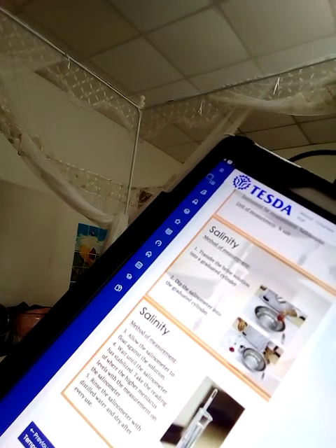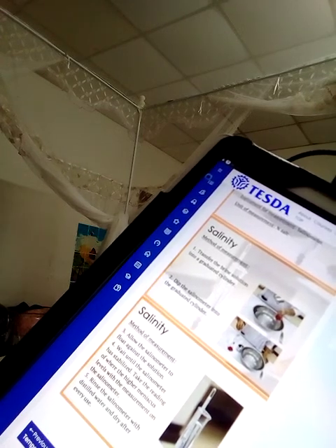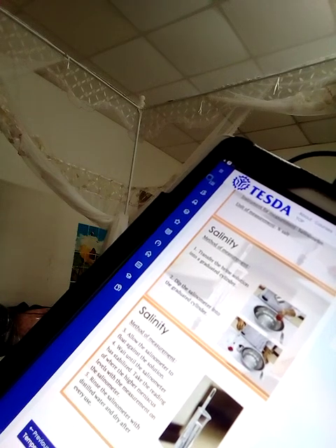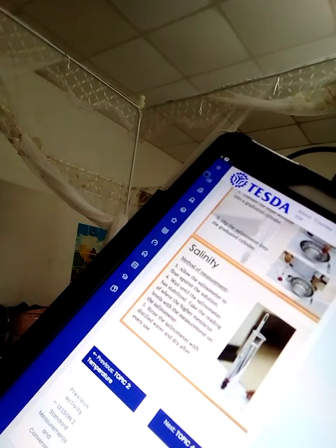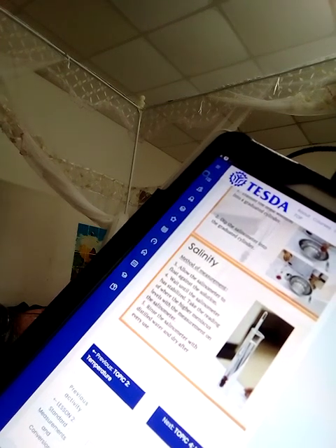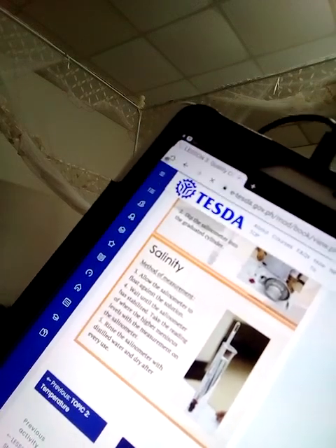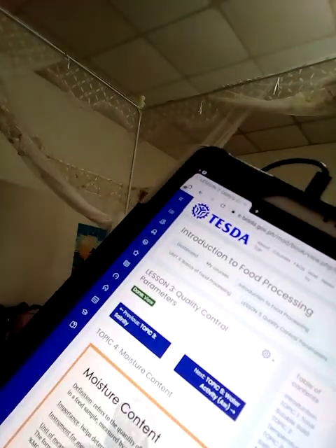Wait until the salinometer has stabilized. Take the reading where the highest meniscus level meets the measurement on the salinometer. Rinse the salinometer with distilled water and dry after use. So, that is the salinometer. Going to topic 4.